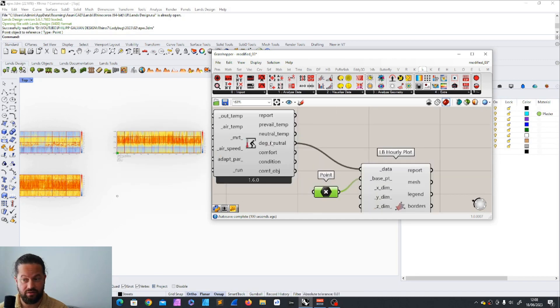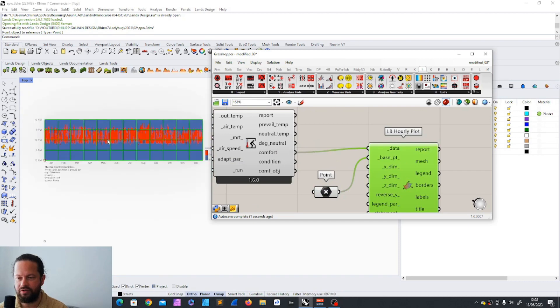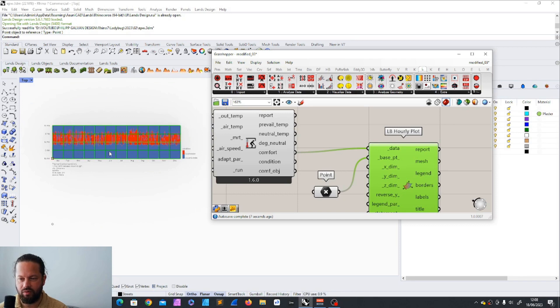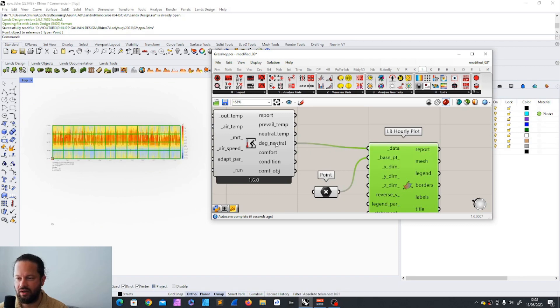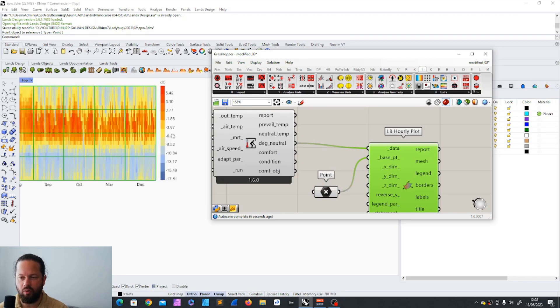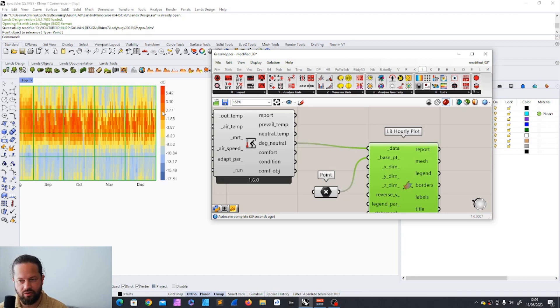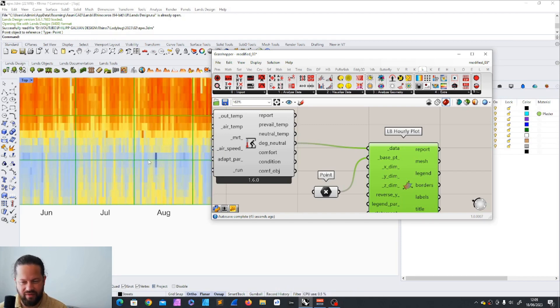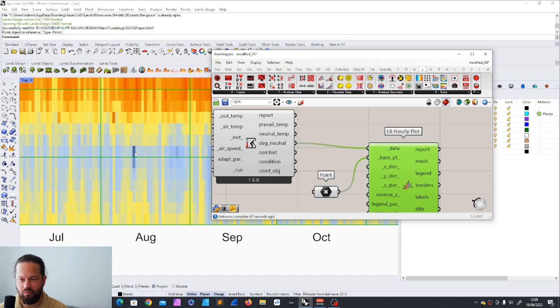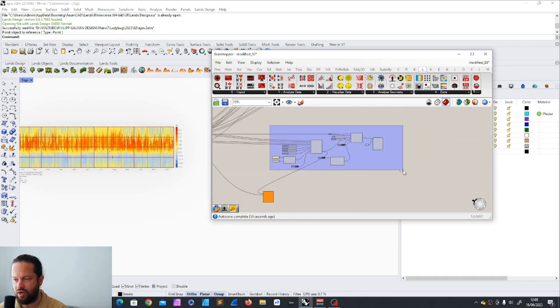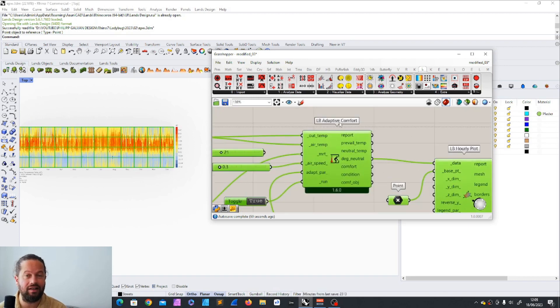Then we just plot everything and look at the temperatures or the comfort. When we looked at the comfort, we saw that whatever is red here is comfortable and what is blue is not. We can also look at the neutral degree — how far is it away from the optimum. For example, the deep orange is closest to maybe 21–23 degrees, or let's say 19–23 degrees. Blue means it's 17 degrees — too cold — which happens only very occasionally, actually just one hour a year. That shows how we used the adaptive comfort with very little knowledge about the actual indoor temperature and very limited data.